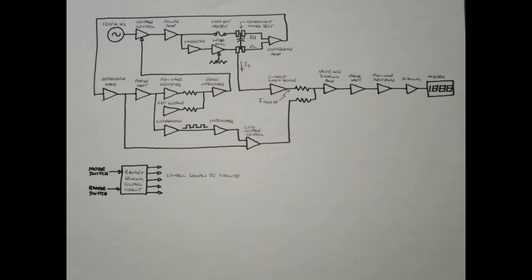This meter uses the phase relationship between reactance and resistance to isolate them from each other. When a sinusoidal AC excitation signal is applied to an impedance, the resistive part of the component responds in phase with the excitation signal, while the reactive part of the component responds 90 degrees out of phase with the excitation.